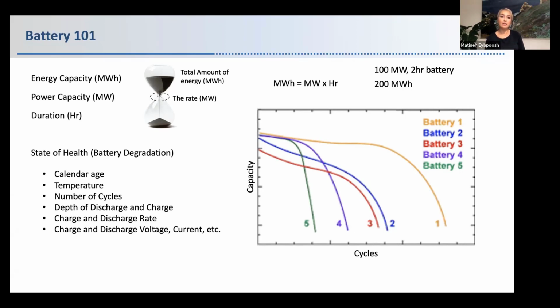There are several factors affecting this. Calendar age is one, just by sitting there batteries degrade because of chemical reactions. Temperature also matters, batteries perform poorly in extreme temperatures, mostly on the hot end, especially when they cycle and work, since they actually create more heat. That's why batteries are usually associated with an on-site HVAC system to cool them down. Other factors include the number of cycles of charge and discharge, the depth of discharge, whether you charge all the way to 100% or keep it around 80%, and the charge and discharge rate, voltage, current, and more.